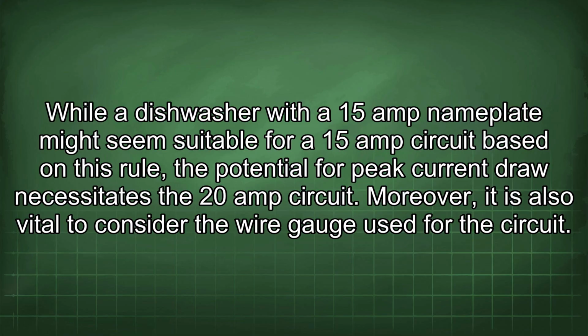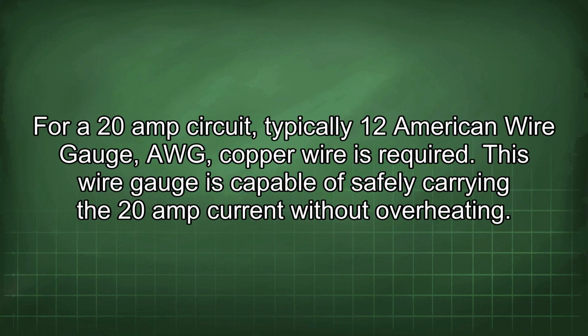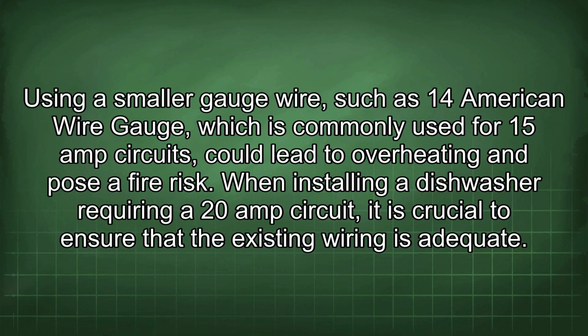Moreover, it is also vital to consider the wire gauge used for the circuit. For a 20-amp circuit, typically 12 American wire gauge (AWG) copper wire is required. This wire gauge is capable of safely carrying the 20-amp current without overheating. Using a smaller gauge wire, such as 14 American wire gauge, which is commonly used for 15-amp circuits, could lead to overheating and pose a fire risk.